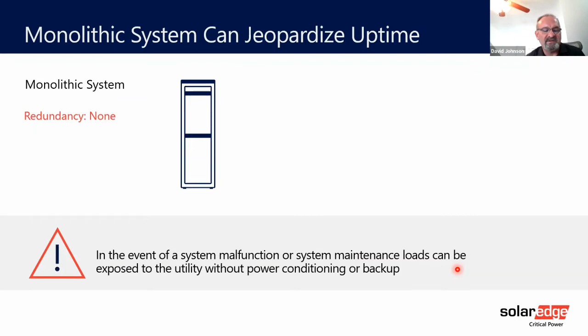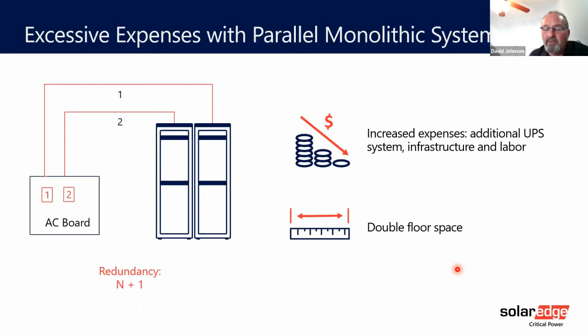With a monolithic system, one unit gives you no redundancy. In the event of a problem, an actual outage, you have the potential loss of your data downstream, or loss of whatever you're protecting. So then we add redundancy. But in a monolithic system, we're doubling the floor space and increased cost, because we're basically doubling the installation.